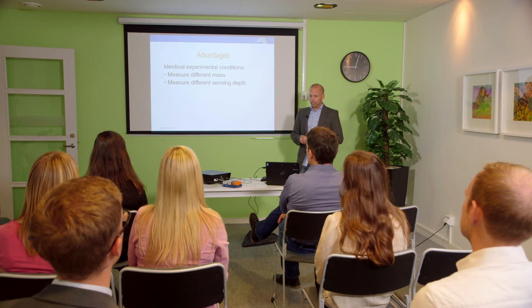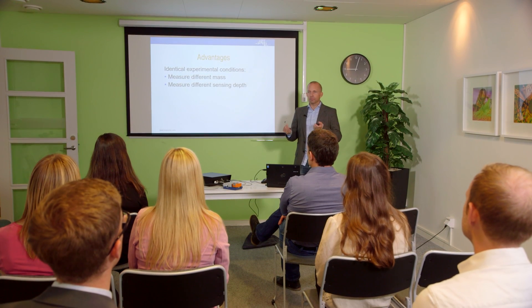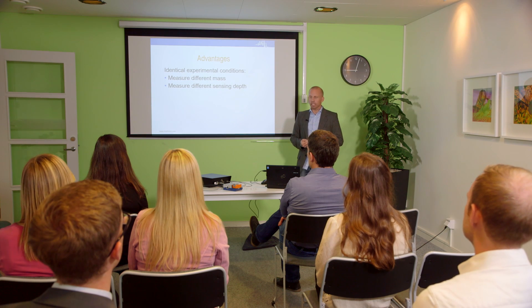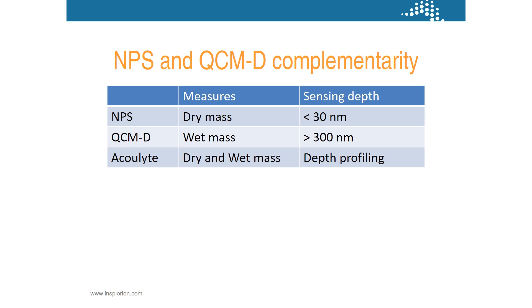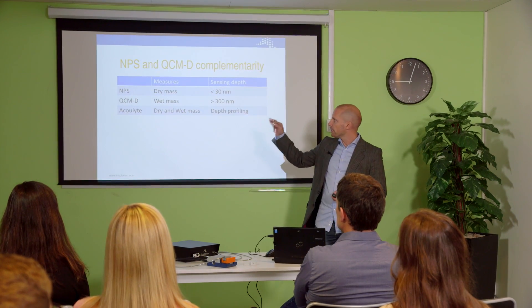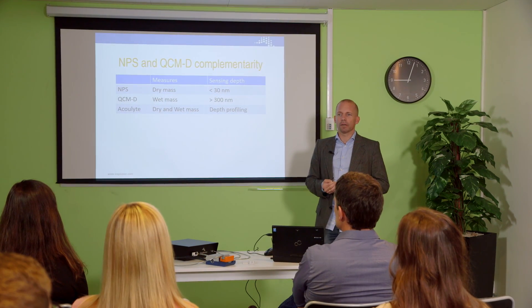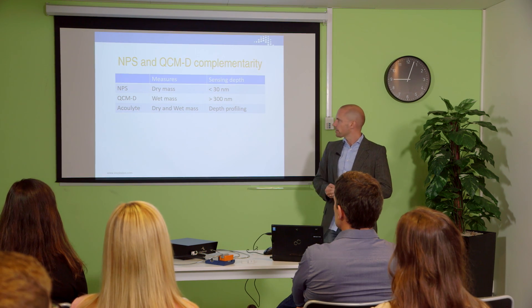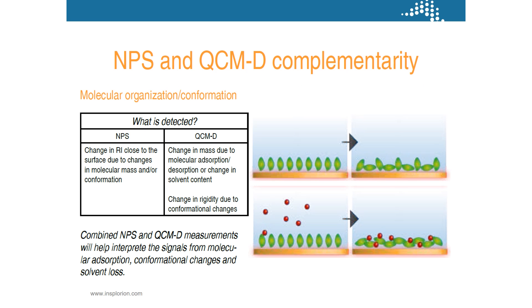We also get different types of information from our two tools. We get different types of mass and we also have different sensing depth when we look at our structures. In short, our technology — the nanoplasmonic sensing — gives dry mass. The quartz crystal microbalance gives wet mass. Together with Acoulyte we can now calculate and get out the dry and wet mass, so for thin films we can basically understand much more about organization and conformational changes.